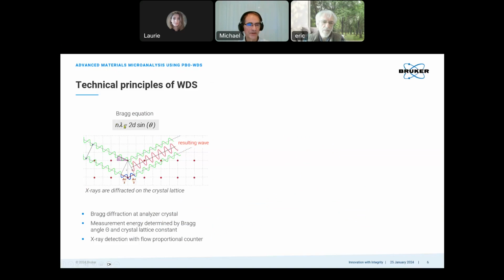We are focusing one energy or wavelength of the X-rays towards our detector, and the parameters inducing that are the crystal lattice parameter D, and the incidence angle of the X-rays, the angle theta. So this graph, this scheme, shows how the X-rays in green, the X-rays generated in the sample, are reflected on the crystal lattice of an analyzer crystal, here symbolized by the red dots.